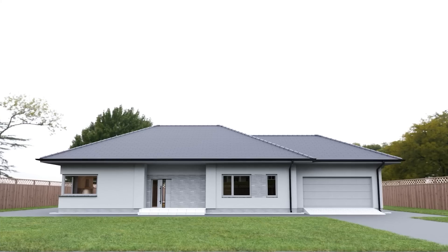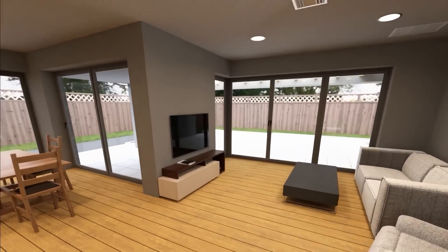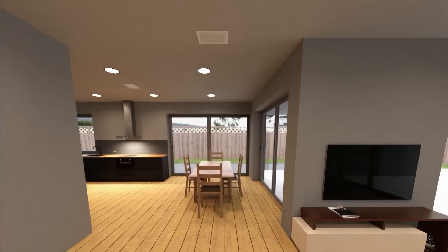Some people will try to solve this by running a ceiling fan, maybe adding a return at the peak. You can do some of those strategies and it can help, but it's usually not your very best bet. Generally speaking, your best bet is just to control the humidity in the space better — sealing all the gaps and cracks from tops of wall plates, using sealed LED cans versus open can lights, sealing around vents and boots. But rather than only doing it in particular spots, look at doing it over the entire structure.